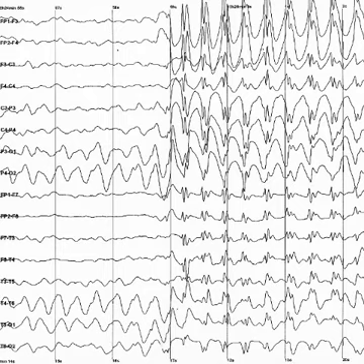A typical adult human EEG signal is about 10 µV to 100 µV in amplitude when measured from the scalp and is about 10 to 20 millivolts when measured from subdural electrodes. Since an EEG voltage signal represents a difference between the voltages at two electrodes, the display of the EEG for the reading encephalographer may be set up in one of several ways. The representation of the EEG channels is referred to as a montage. Sequential Montage: Each channel represents the difference between two adjacent electrodes. The entire montage consists of a series of these channels. For example, the channel FP1-F3 represents the difference in voltage between the FP1 electrode and the F3 electrode. The next channel in the montage, F3-C3, represents the voltage difference between F3 and C3, and so on through the entire array of electrodes.